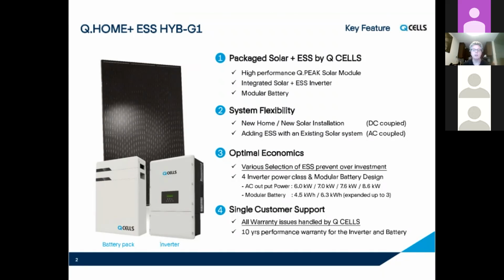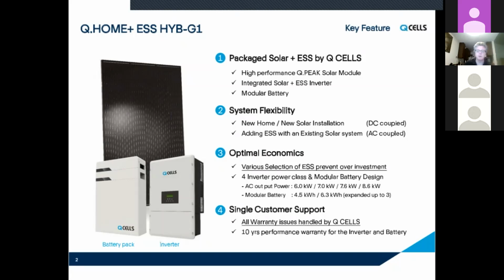So, how big of an inverter do you need? We've got basically four inverter sizes here. The first three, 6 to 7.6, are going to sit on a 40 amp breaker. The larger inverter, the 8.6 kilowatt inverter, needs to sit on a larger 60 amp breaker. When thinking about the size of your main service panel, these first three inverter sizes would support anything on a 200 amp main panel, and the 8.6, our heavy duty inverter, is going to need to sit on likely a 400 amp main service panel.